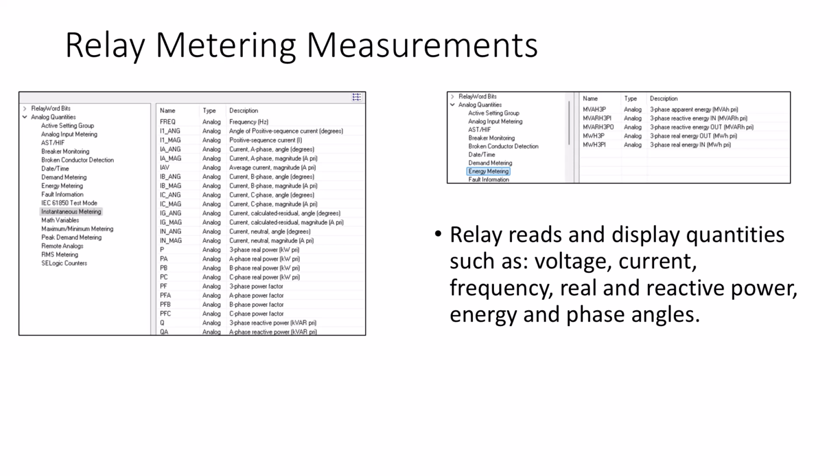This relay is capable of measuring and displaying a wide range of quantities, including RMS bus voltage, RMS line current, three-phase power, and energy consumption. In addition, the relay calculates fundamental voltage and current magnitudes along with their corresponding phase angles. For our introductory example, we'll focus on measurements related to a single-phase load.